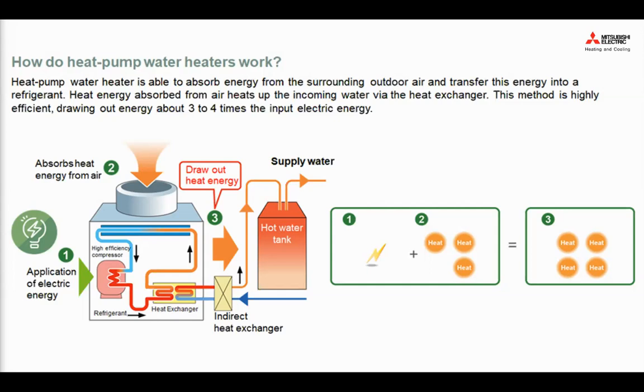Okay. Yes. What is the lowest or maximum delta T the unit can operate at? So from our factory data, the entering water temperature can be 49 degrees C, right? And then you will still produce hot water at 70 degrees C. So delta T is leaving water temperature versus entering water temperature. So 70 minus 50, so 20 degrees C. Yeah, that will be a really good cap on the unit.